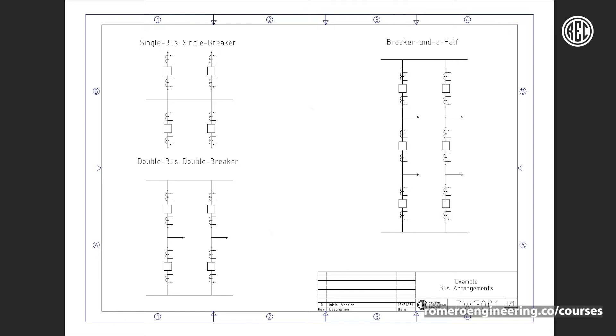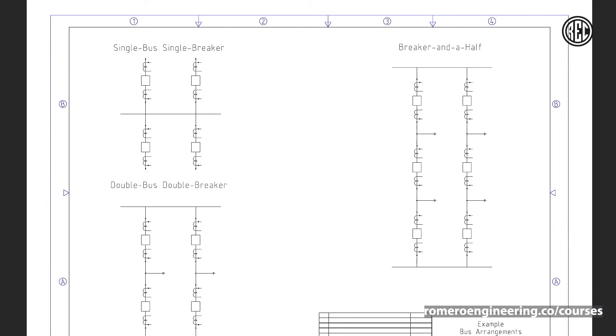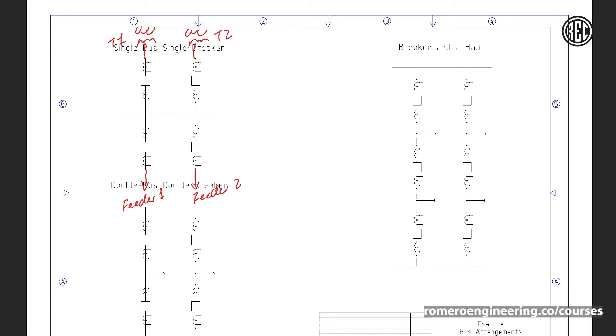Let's talk about the single bus, single breaker — also called a straight bus configuration. This is the most economical and simple design, used particularly at low voltage levels, in distribution substations or sub-transmission substations. For example, at a distribution substation we might have two transformers, T1 and T2, each connecting through a breaker to feeders — feeder one and feeder two. As you can see, this is the most simple design, connecting all sources to one common point of interconnection.